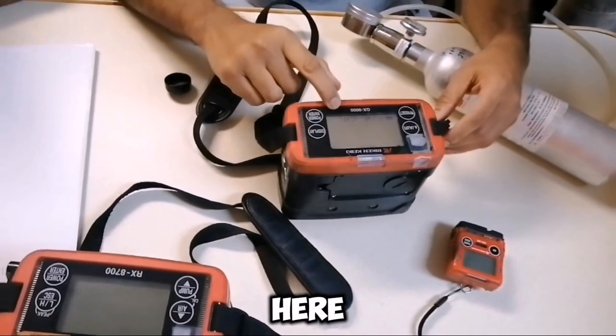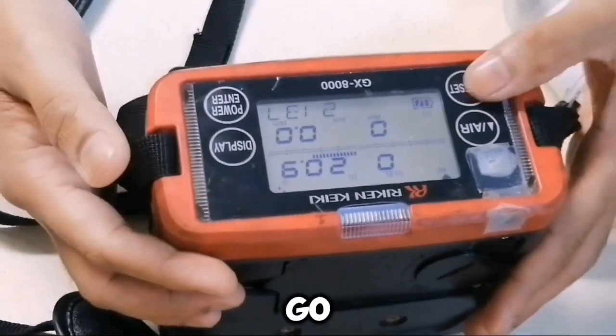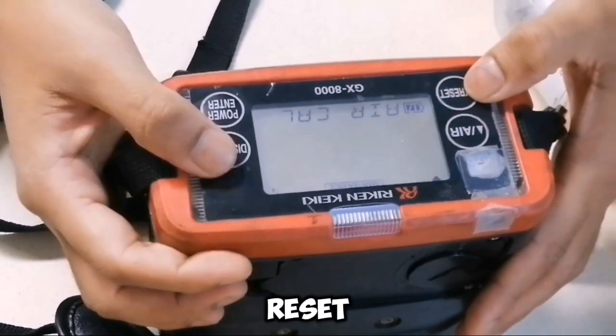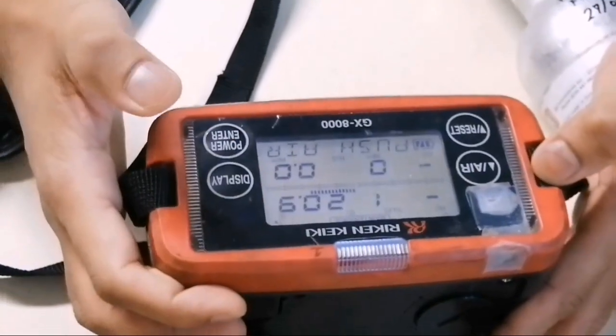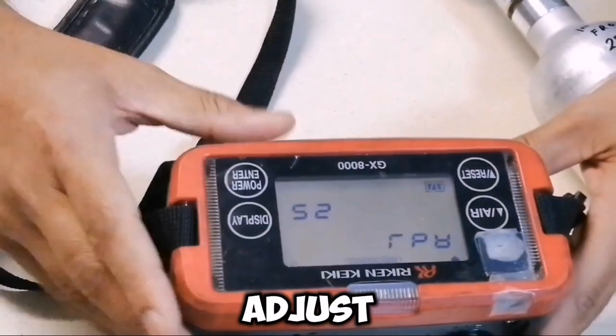First you have to do air cal. So you have to press Reset and Display — it will go into air cal mode. Then you can press enter and push. I'm holding it and it is showing adjustment. Around 30 seconds to adjust the gases.